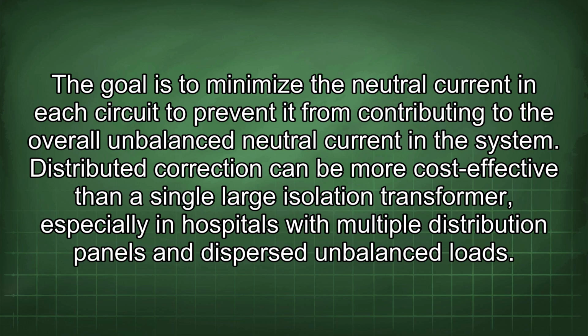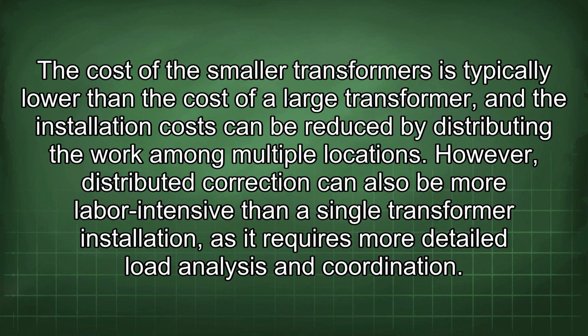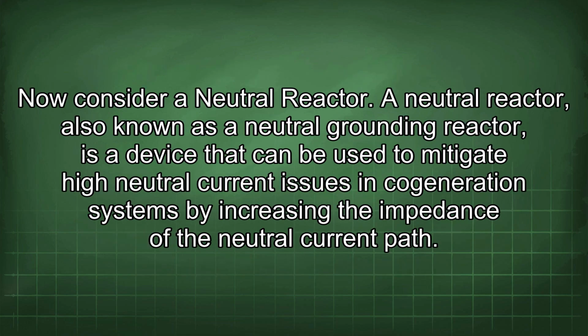Distributed correction can be more cost-effective than a single large isolation transformer, especially in hospitals with multiple distribution panels and dispersed unbalanced loads. The cost of the smaller transformers is typically lower than the cost of a large transformer, and the installation costs can be reduced by distributing the work among multiple locations. However, distributed correction can also be more labor-intensive than a single transformer installation, as it requires more detailed load analysis and coordination. Now consider a neutral reactor.